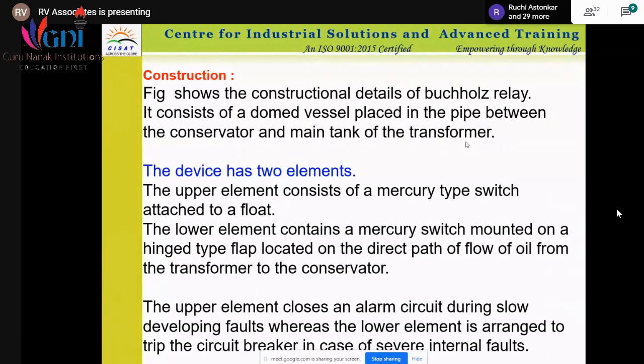This Buchholz relay has two elements. It has a float. That float will give you one alarm, and the other is the trip, based on the seriousness of the fault.